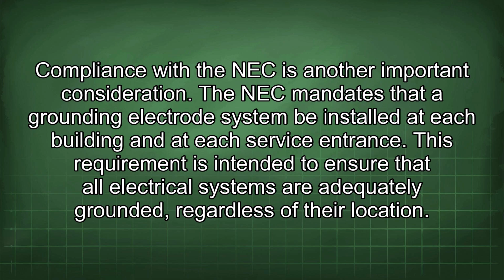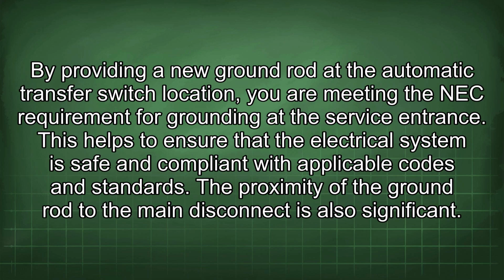Compliance with the NEC is another important consideration. The NEC mandates that a grounding electrode system be installed at each building and at each service entrance. This requirement is intended to ensure that all electrical systems are adequately grounded, regardless of their location. By providing a new ground rod at the automatic transfer switch location, you are meeting the NEC requirement for grounding at the service entrance. This helps to ensure that the electrical system is safe and compliant with applicable codes and standards.